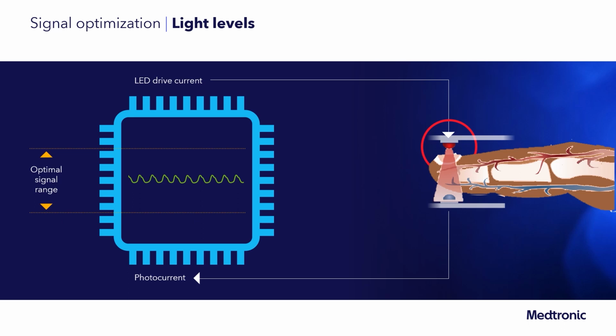The second case that we can have is when the light signal that we detect is so high that it actually saturates our electronics. What we mean by that is that as more light is detected, our electronics can no longer measure that increase. They've maxed out the measurement capability. And so in this situation, what we need to do is to take that light signal and decrease it back into our optimal signal range. There are two ways that we can get that signal to decrease into our range. One, we could send less current to the LED, or we could amplify that current less.